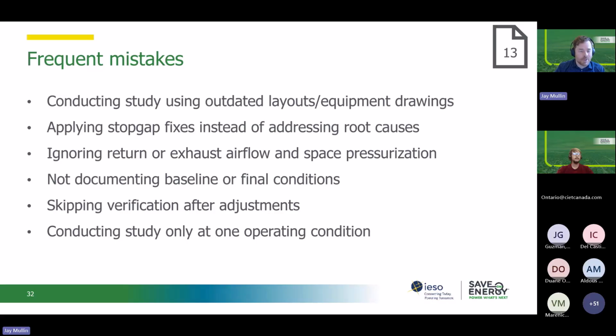Another issue is ignoring return, exhaust airflow, and space pressurization. Make sure to include your supply, return, and exhaust pressure relationships in every assessment. Don't measure one in isolation. Often, it's not fully documented in terms of the baseline and final conditions. So it's really important to record your airflow, pressure, damper position, and equipment status before and after any adjustments to ensure repeatability. Because if a year or two later those pressure issues start popping up again, you can refer back to that before and after state and see if things have reverted. It can shortcut any corrections later on.